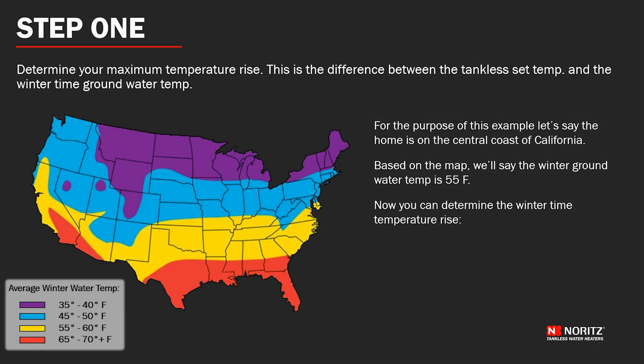Step one is where you determine the maximum temperature rise. This is the difference between the tankless set temperature and the wintertime cold water temperature. You may reference the map below or simply measure your cold water in the wintertime to find out. For this example, let's say the home is on the central coast of California. Based on the map we'll say the winter groundwater temperature is 55 degrees Fahrenheit.